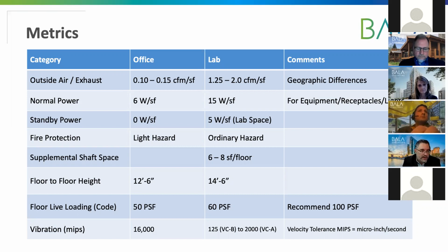We're generally seeing values between 1 to 2 CFM per square foot, predicated on the types of labs we're dealing with, whether biological or chemical in nature. Chemistry type labs tend to have more fume hoods and a denser layout, so they're closer to the 2 CFM range. A biological based laboratory, which may rely on a combination of fume hoods, or zero fume hoods, and biological safety cabinets, will be on the lower end, at 1 to 1.25 CFM.